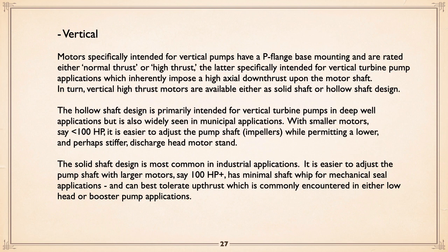There are two different designs that you can get, either solid shaft or hollow shaft. A hollow shaft is primarily intended for vertical turbine deep well applications, but a lot of municipalities use it. Come back to that. With smaller motors, say below 100, it's easier to adjust the pump shaft because it's about the right height. With say a 75 horse motor, you can reach over and adjust the shaft that's sticking through the hollow motor. And the discharge head can be built a little bit lower, so it's a bit stiffer.